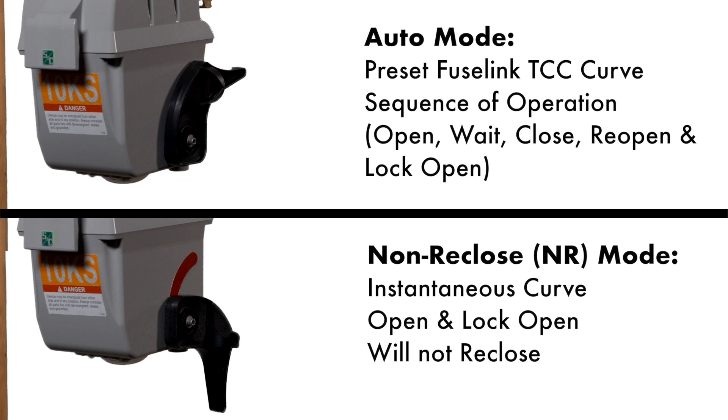In the auto mode, the VacuFuse Interrupter will respond to fault current according to its preset fuse link TCC curve. The interrupter will behave according to the standard sequence of operation. It will open, wait a preset number of seconds, close once, and if the fault is still on the line, will reopen and lock open. If another fault occurs during its sequence reset time, the interrupter will immediately open and lock open. The VacuFuse self-resetting interrupter will not drop out of the mounting and will remain upright in the cutout mounting.